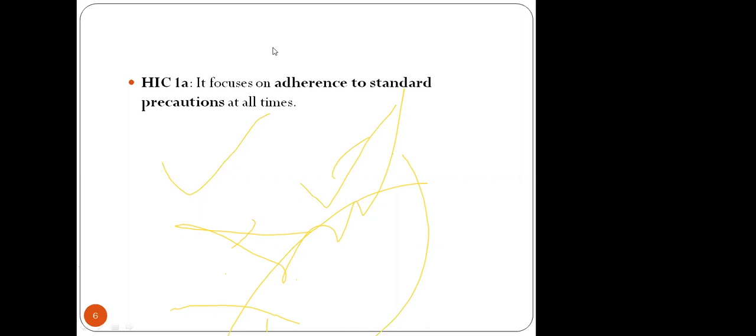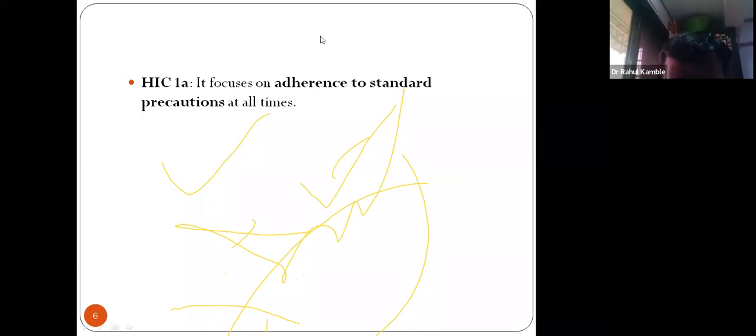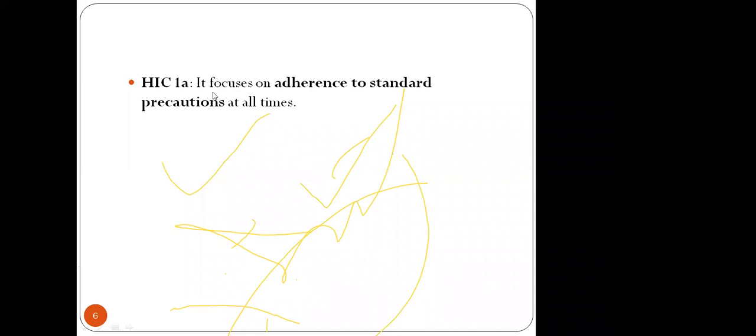Okay. Second thing, sir, the autoclave time period. According to what I've studied somewhere in ISO 15189, they have said the time to be 1 hour. Is it 30 minutes or 1 hour? This was a common non-conformity raised in most healthcare settings during COVID-19. Yes, so 20 minutes is the sterilization. But if you refer to the present MPCB guideline for biomedical waste, it is 1 hour. 1 hour is required for sterilization of biomedical waste. So we should go for 1 hour only.